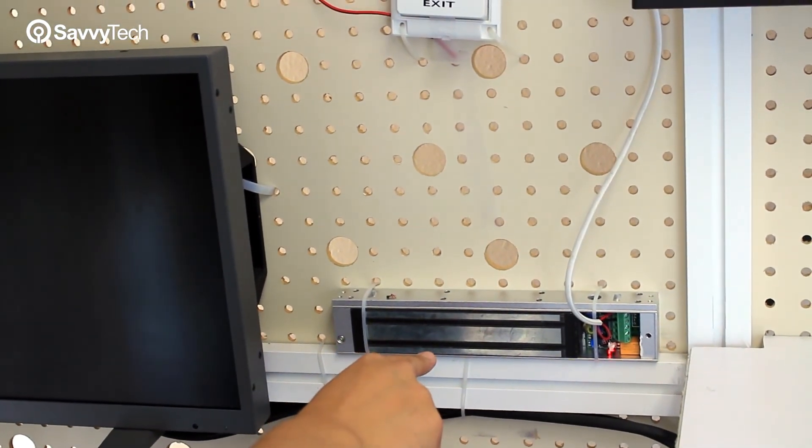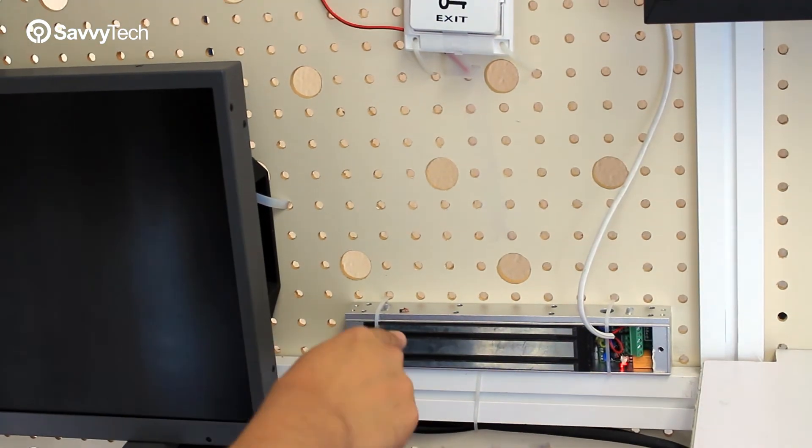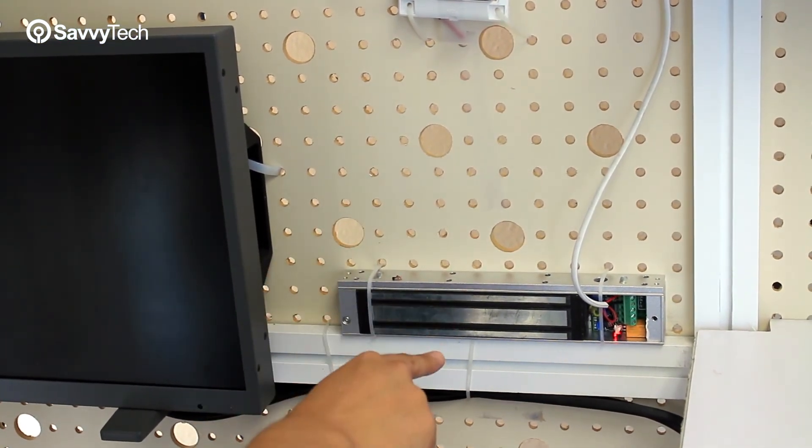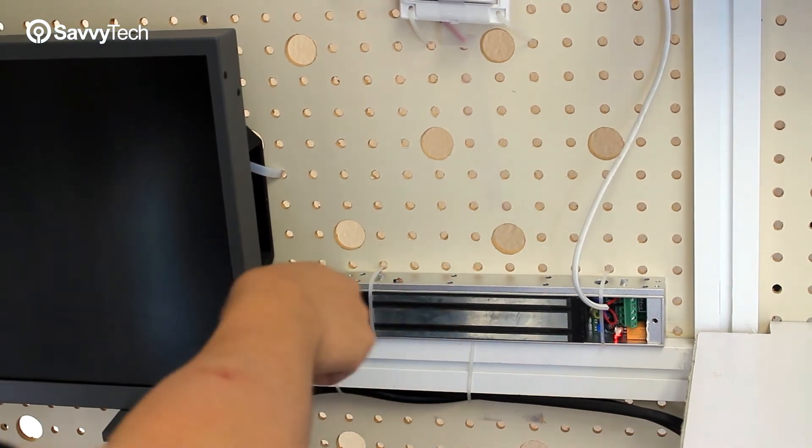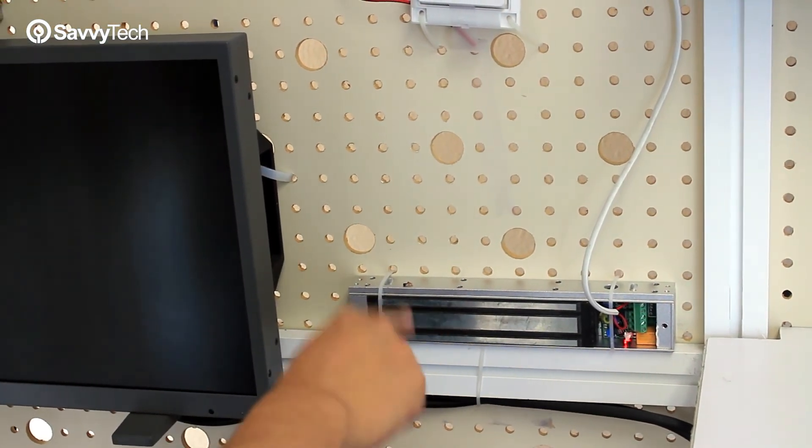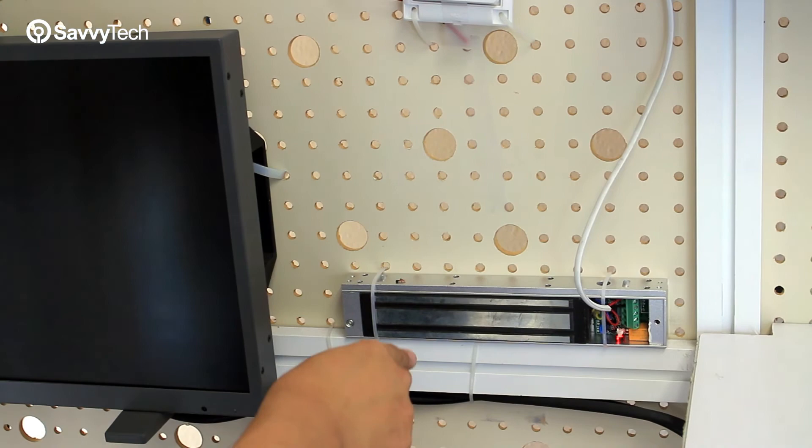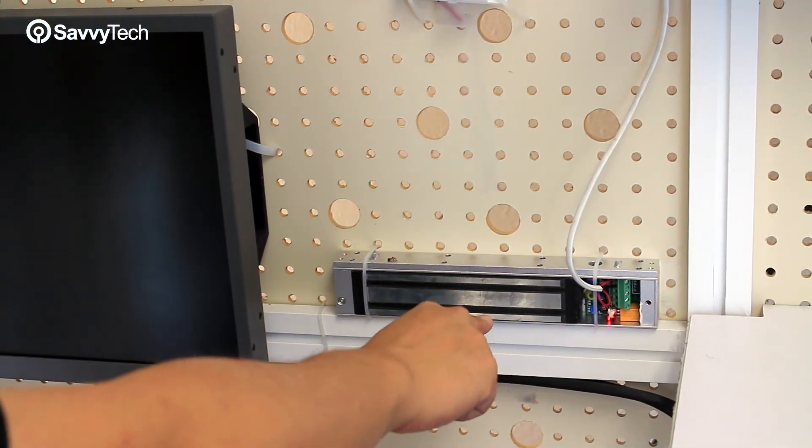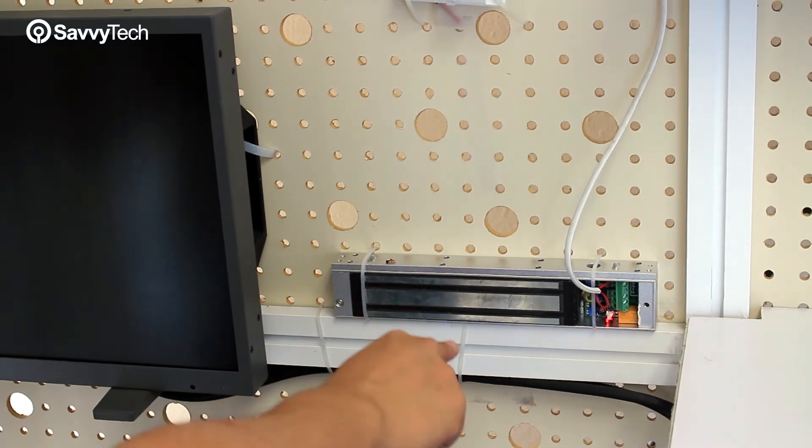One thing that you want to keep in mind is that constant power has to be supplied to the door lock in order to keep it closed. If power is cut off, then the door lock will be released. It's also good to know that because in case of emergencies, if the programming does not work, then cutting power to the door lock will be able to release it to allow people to exit the building.